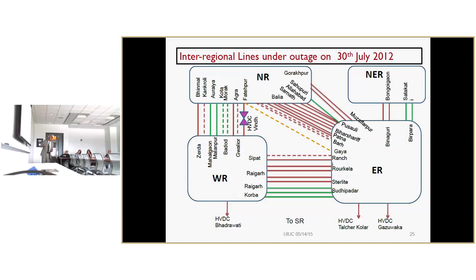And there were a few lines connected between the western region and the northern region. And there is a line which is coming from Agra. Agra is famous for the Taj Mahal. Gwalior and Bina, that is one line, a 400 kV line. Finally, one by one, they tripped because of some fault, and only this line was carrying almost 1400 megawatt. The SIL of a 400 kV line is 691 megawatt.